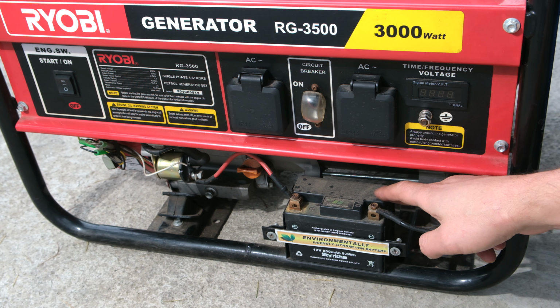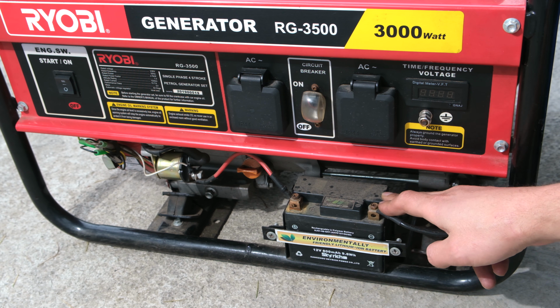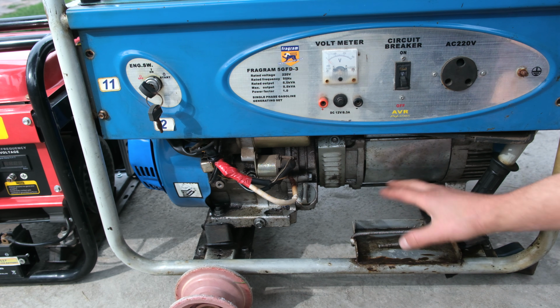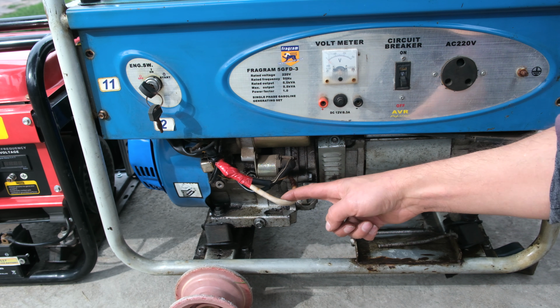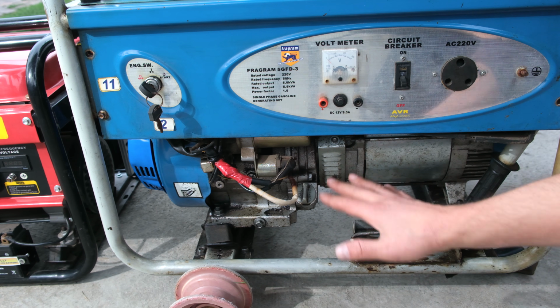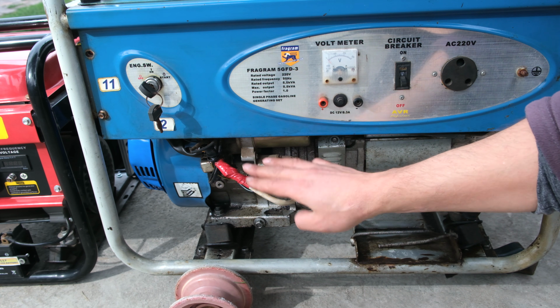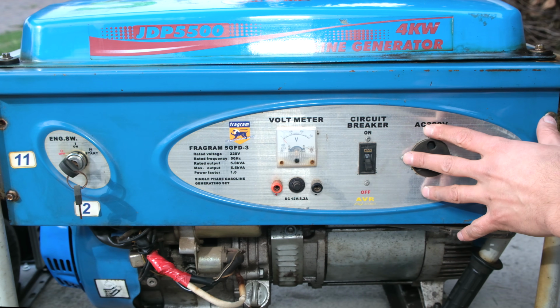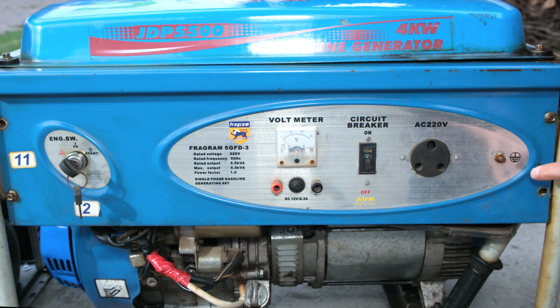Many generators are fitted with a lead acid battery to have a battery start. Often these batteries go flat and they no longer work. In the case of this generator, the battery has been removed. That means that there would have been bare wires. So if there are any bare wires on your generator, make sure they are strapped and put out of the way. A generator should be used as an isolated circuit and it should always be earthed.